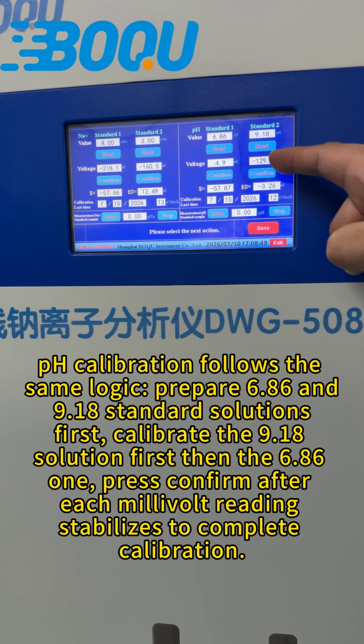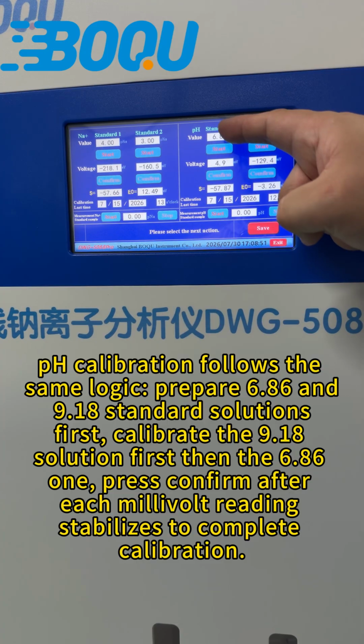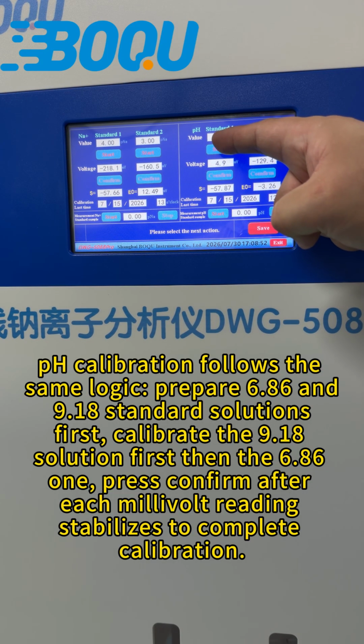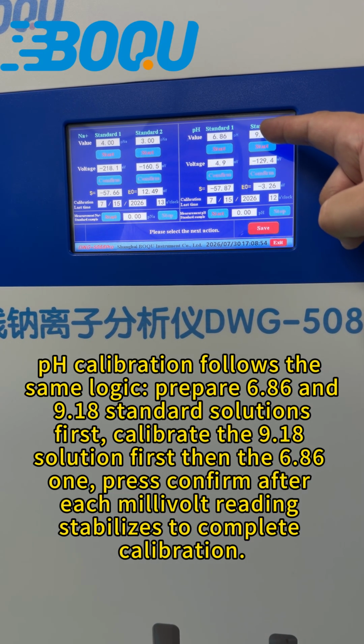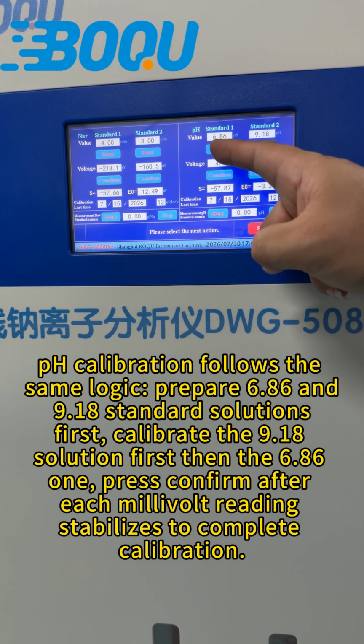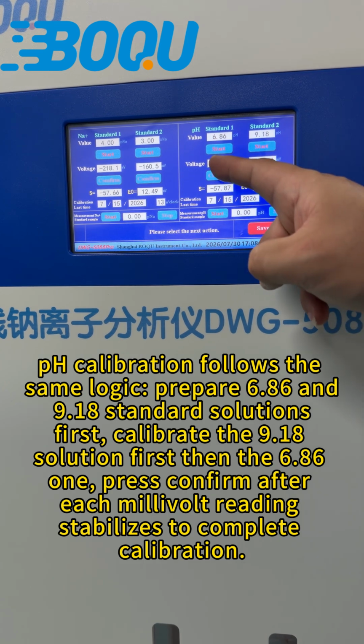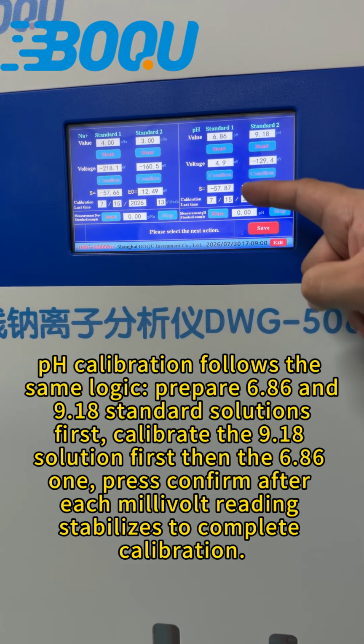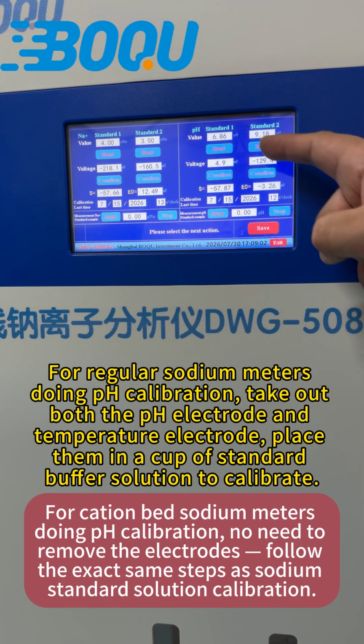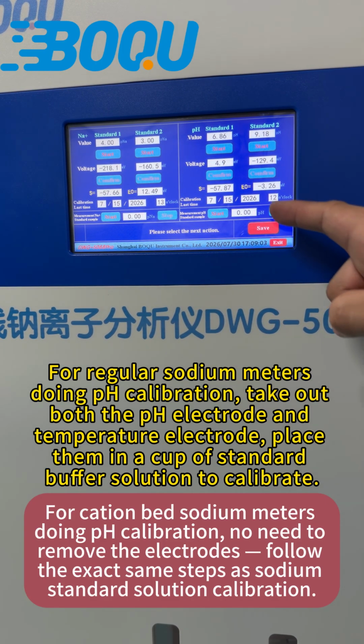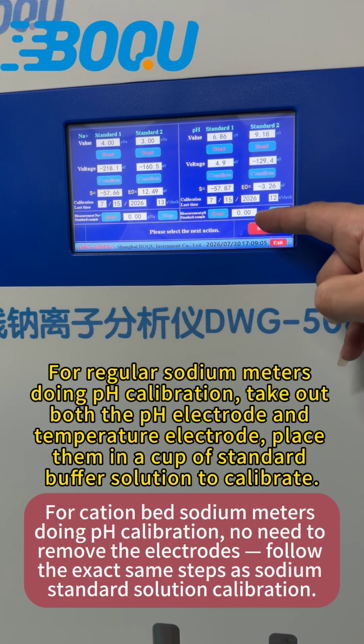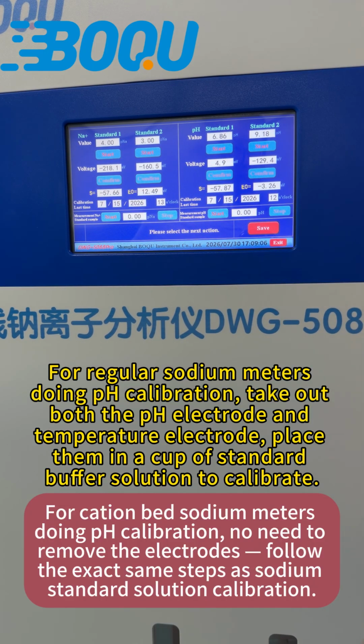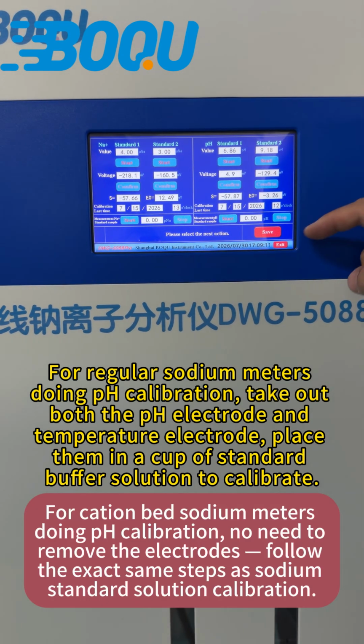pH calibration follows the same logic. Prepare 6.86 and 9.18 standard solutions first. Calibrate the 9.18 solution first, then the 6.86 one. Press confirm after each millivolt reading stabilizes to complete calibration. For regular sodium meters doing pH calibration, take out both the pH electrode and temperature electrode. Place them in a cup of standard buffer solution to calibrate.